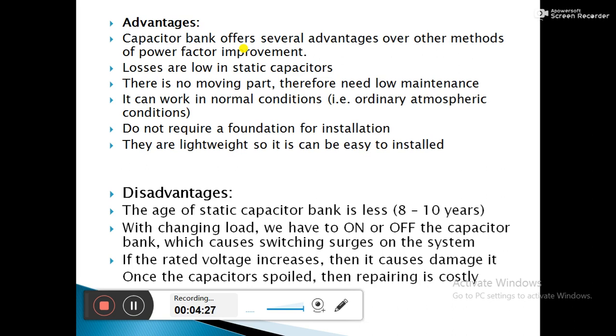The disadvantages of static capacitors are: the age of a static capacitor bank is less — only 8 to 10 years — after which it needs to be replaced. With changing load, we have to switch the capacitor bank on and off, which causes switching surges on the system. Additionally, if the rated voltage increases, it can cause damage, and once a capacitor is spoiled, repairing is costly and uneconomical.